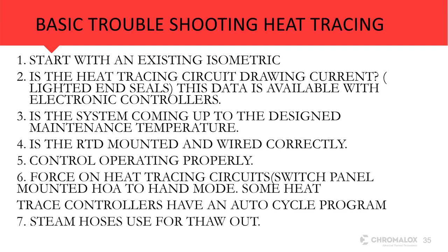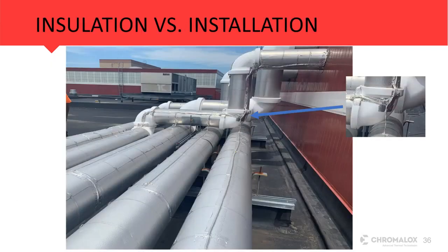This is a recent installation, a photo we just got, which kind of says it all. Someone tried to take the heat tracing and install it on the outside of the insulation. Obviously, this is not going to work. So we need to make sure that the heat tracing is under the insulation. It's just kind of unbelievable what some people will do, but this obviously is not going to work. So make sure that you stick it underneath the insulation.